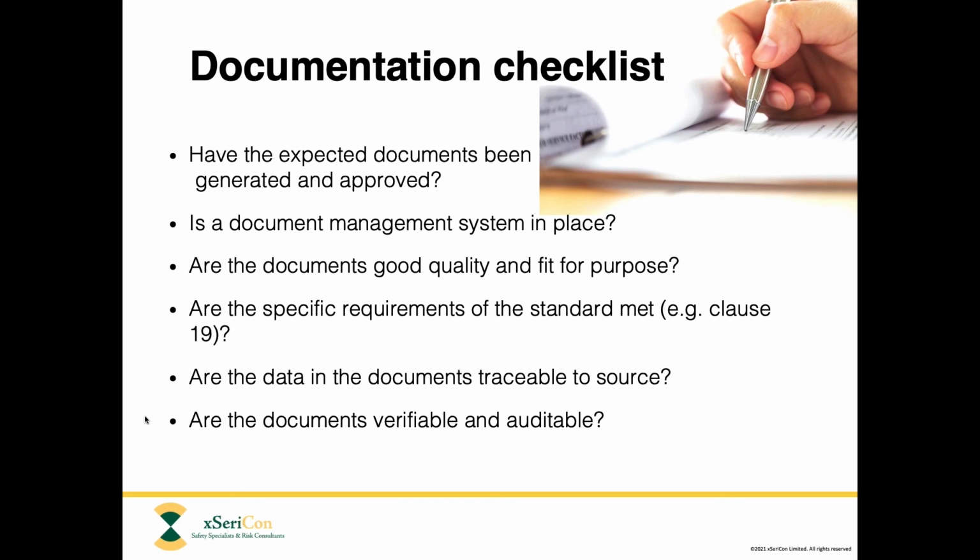There are a few specific requirements in the standard. For example, IEC 61511, Part 1, Clause 19, lists some generally not too difficult to achieve requirements relating to the documents. Relating to the documents, we would like to confirm that those specific requirements are met. And one of them in particular is we would like to confirm traceability.